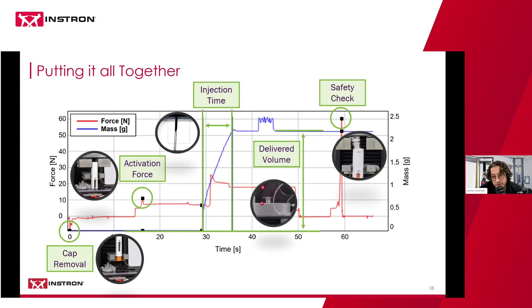You have the option to do either just a go to a set load to ensure there's no separation of the device, or to make sure that there's no excessive movement of the needle shield, or do a full defeat force where you actually try and cause a failure of the needle shield. That can be done on the system, which was a big ask from customers who in the past had to use a totally separate dedicated system to do defeat force.